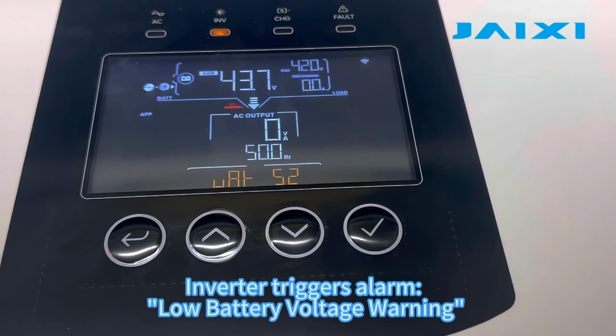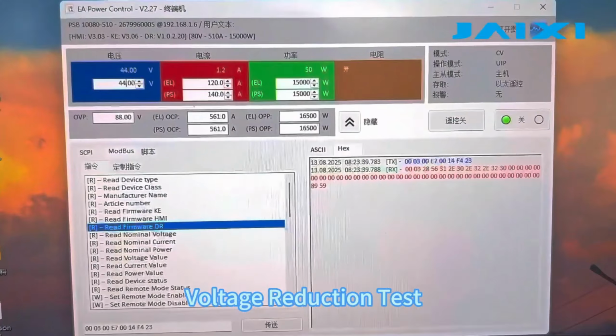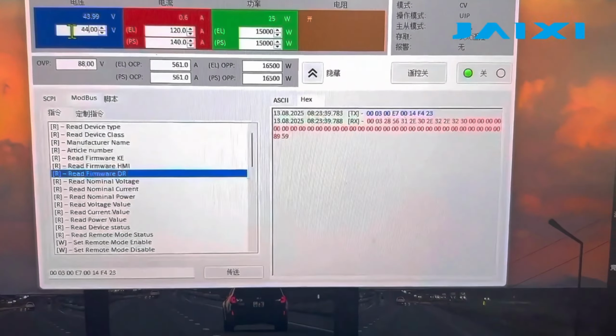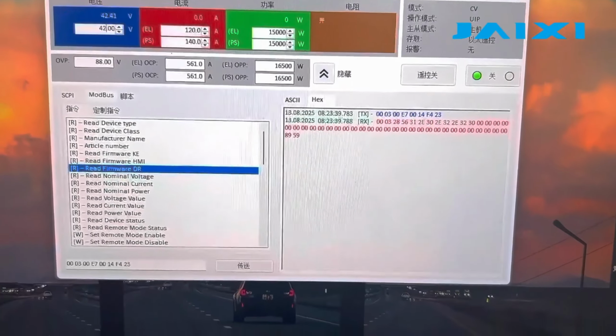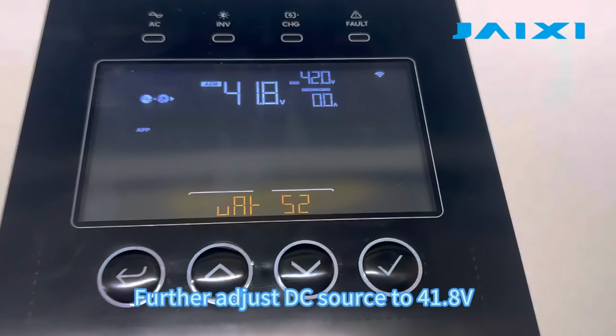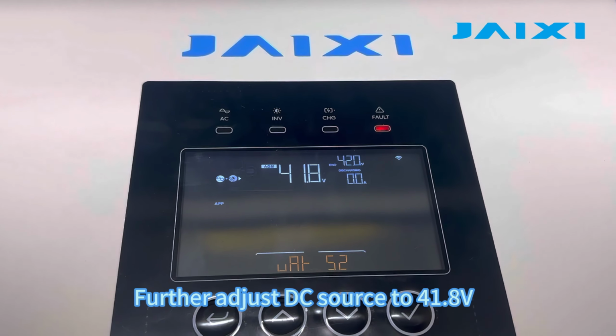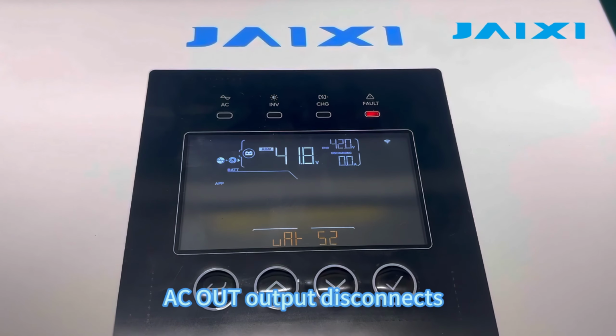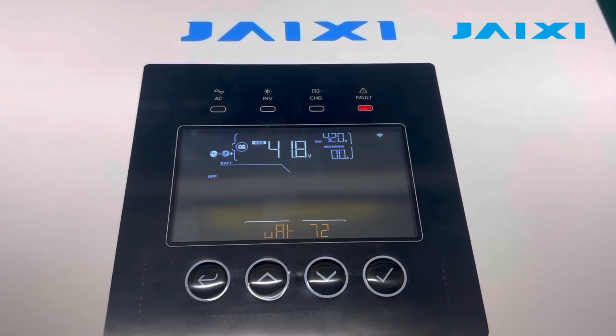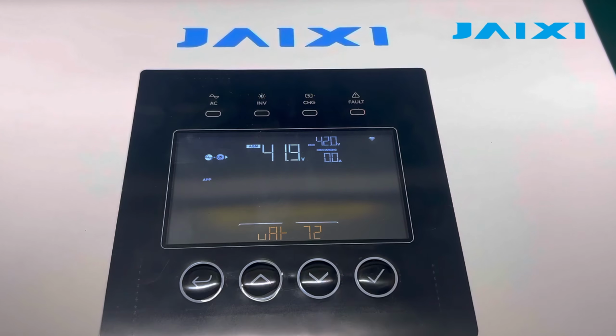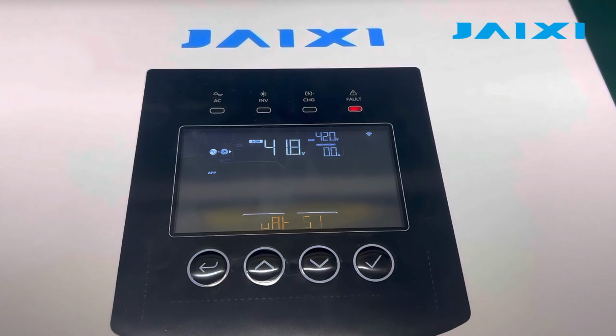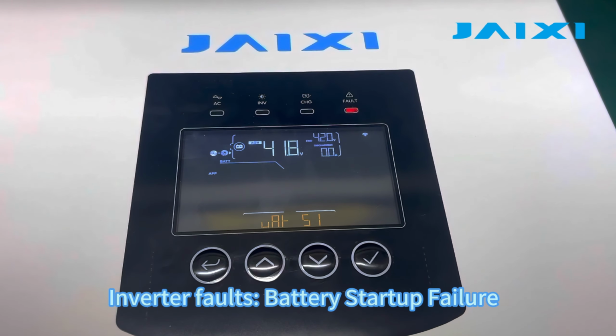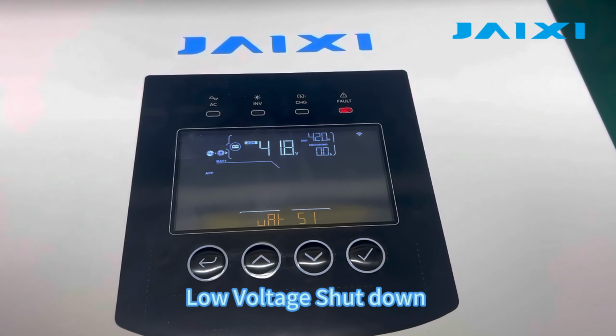Inverter triggers alarm. Low battery voltage warning. Voltage reduction test. Further adjust DC source to 41.8 V. AC out output disconnects. Inverter faults, battery startup failure, low voltage shutdown.